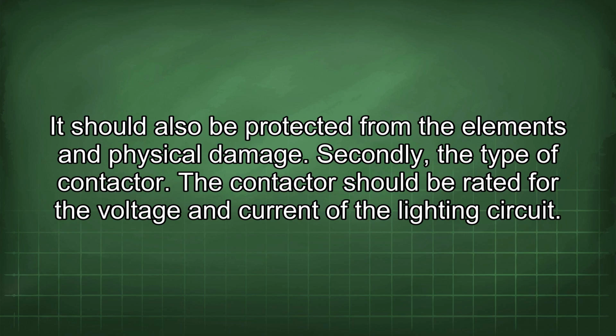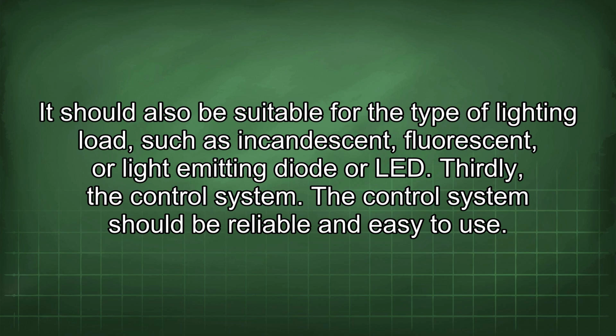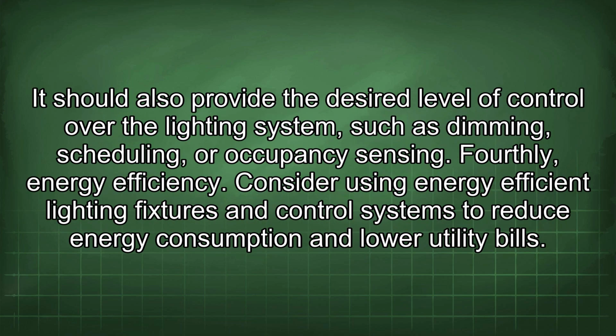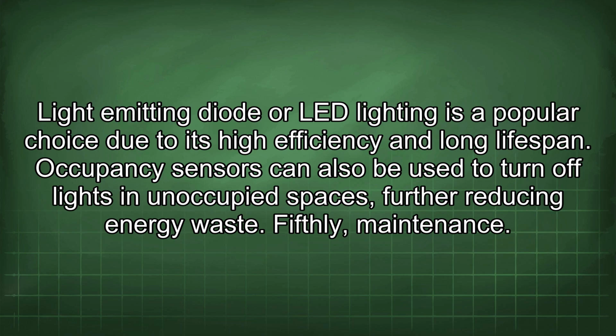Secondly, the type of contactor. The contactor should be rated for the voltage and current of the lighting circuit. It should also be suitable for the type of lighting load, such as incandescent, fluorescent, or light-emitting diode or LED. Thirdly, the control system. The control system should be reliable and easy to use. It should also provide the desired level of control over the lighting system, such as dimming, scheduling, or occupancy sensing. Fourthly, energy efficiency. Consider using energy-efficient lighting fixtures and control systems to reduce energy consumption and lower utility bills. Light-emitting diode or LED lighting is a popular choice due to its high efficiency and long lifespan. Occupancy sensors can also be used to turn off lights in unoccupied spaces, further reducing energy waste.